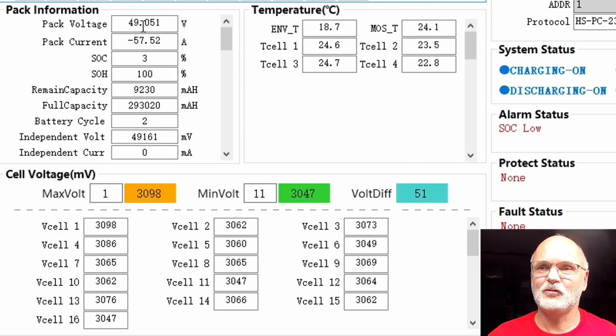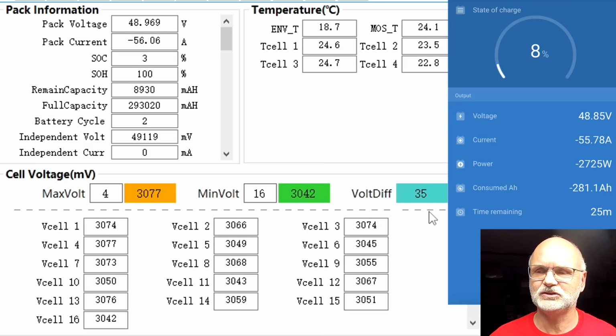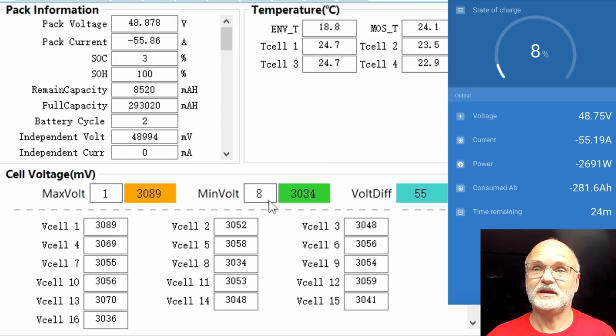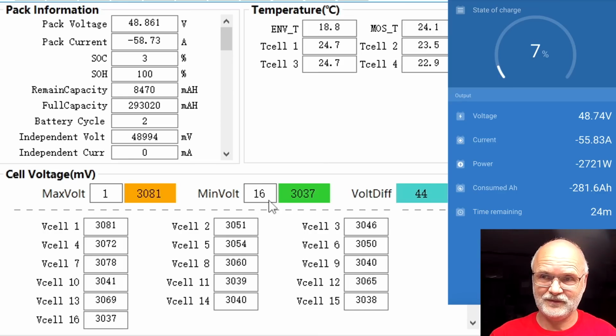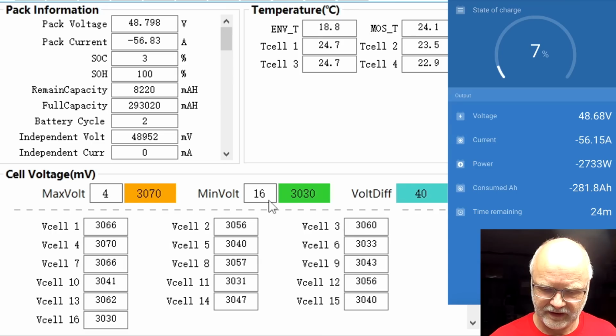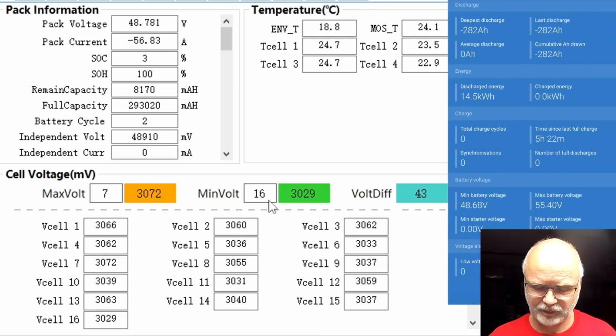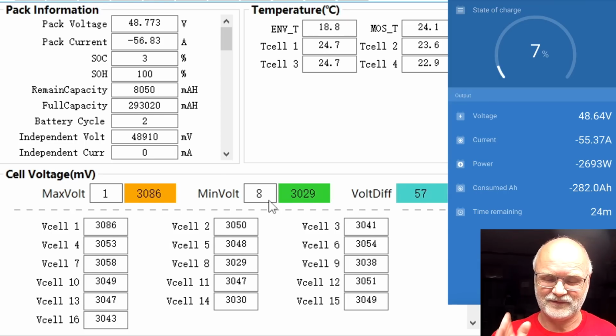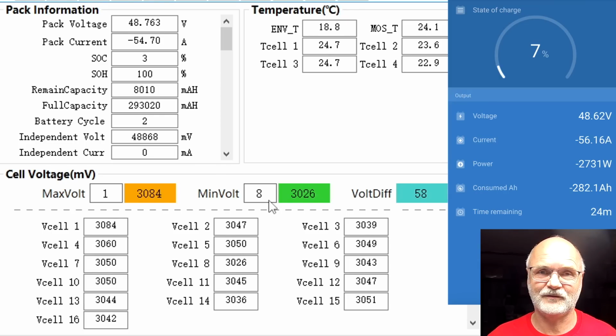We are down to 48 volts, 3%. We're at 50 millivolt deviation at the moment, still discharging with 56 amps, and the cells are still changing here. You can see number 1, number 7, number 4 as the maximum, and here number 8, number 9, or 16 now. So this is good. That means the pack is well balanced, still in the lower area of the curve as well. We have discharged 14.5 kilowatt hours, so we will roughly get into the same result again as in the first test.